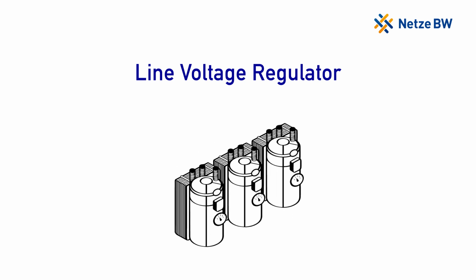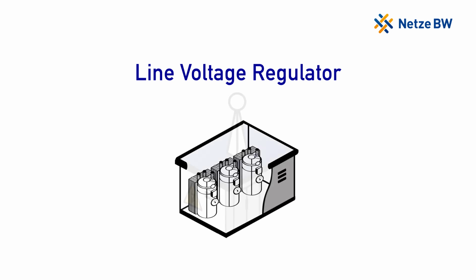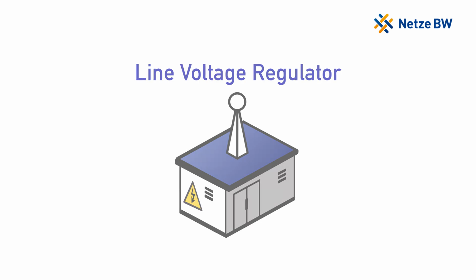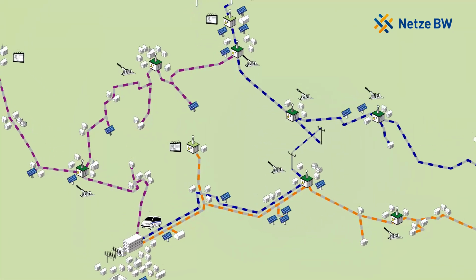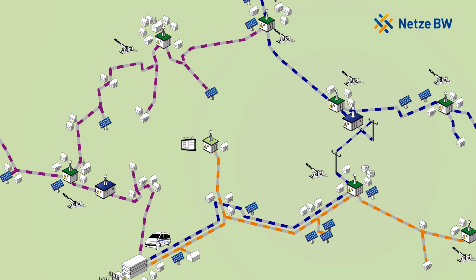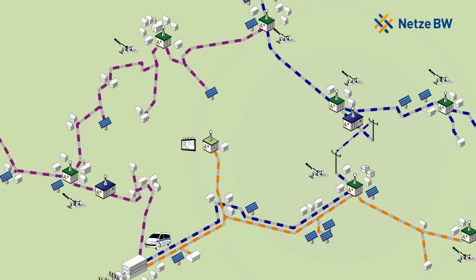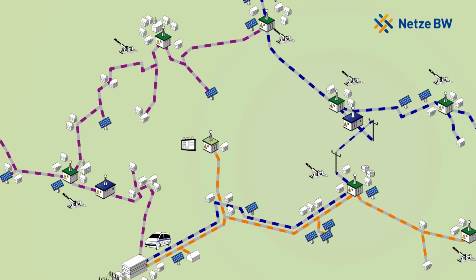This makes it possible to accommodate higher power feed-in to the existing grid from renewable energy sources without having to physically expand the grid. 2 medium voltage line regulators from Siemens have been installed in Niederstetten. These are the first units of their kind anywhere in Europe.